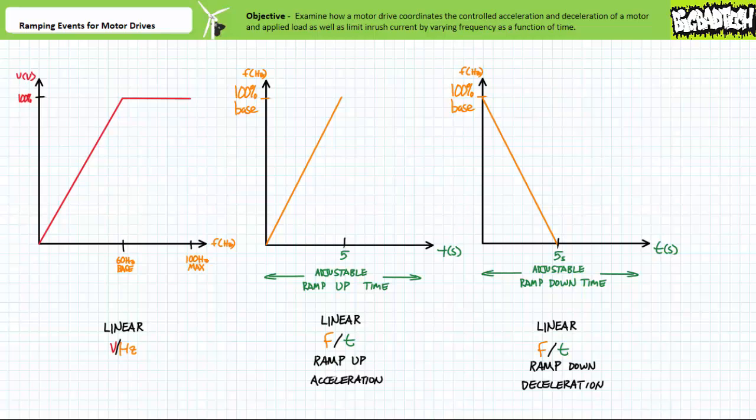Acceleration and deceleration ramp-up and ramp-down times are often user-customizable within a given range. Consider a motor drive with the same simple linear volts per hertz profile, where excitation frequency is ramped from zero to the base frequency over a relatively snappy five seconds. When the run command is asserted, excitation frequency would be ramped from zero to 60 hertz, only this time over five seconds. Voltage would also be ramped from zero to 100% over the same five-second period. Whatever driven load is attached to the motor is briskly accelerated during this much shorter and steeper acceleration period.